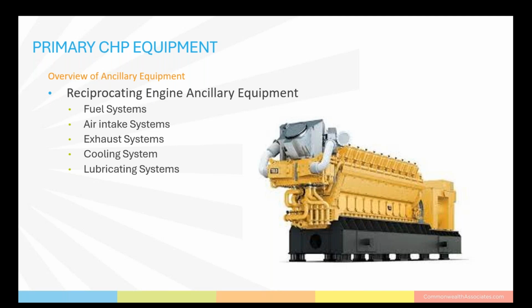Reciprocating engines will have the generator mounted on the end of the engine and will require maintenance pull space on that end. They will most likely include the following ancillary equipment: fuel pumps, fuel filters, fuel injectors, air filters. You'll need air compressors for both instrument air and potentially starting air, and you may have turbochargers. There needs to be exhaust manifolds, exhaust silencers, potentially catalytic converters, radiators, cooling fans, water pumps. And in regards to oil, you're going to have oil pumps, filters, coolers, and some kind of storage.